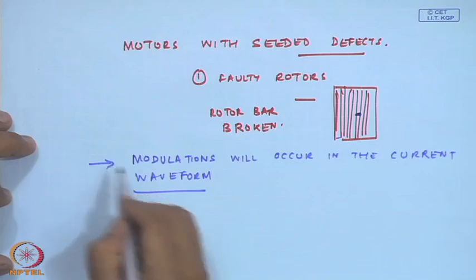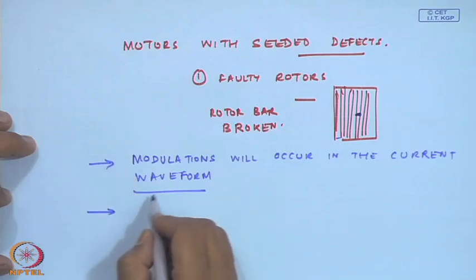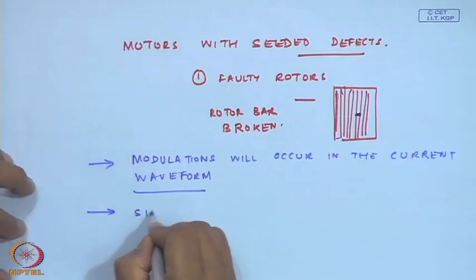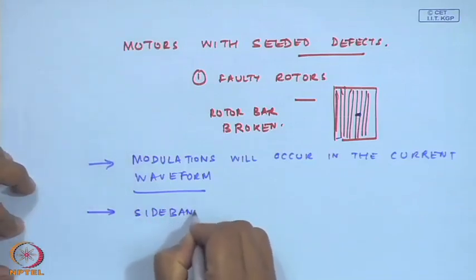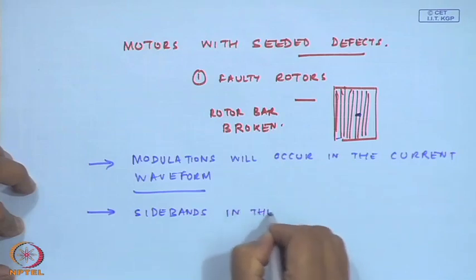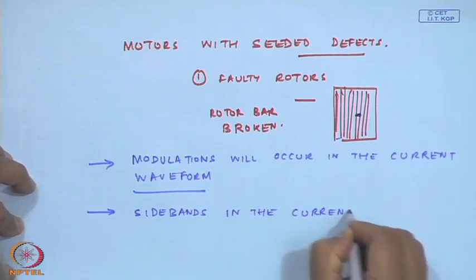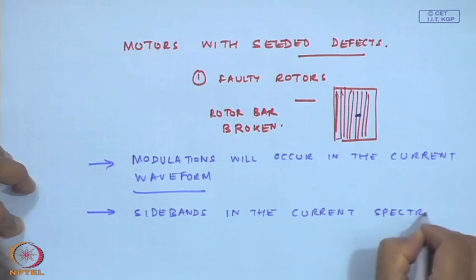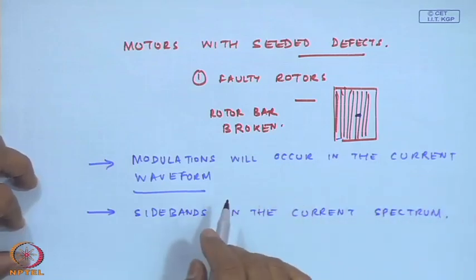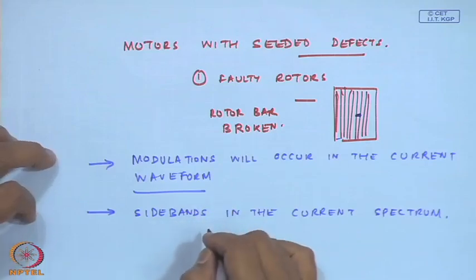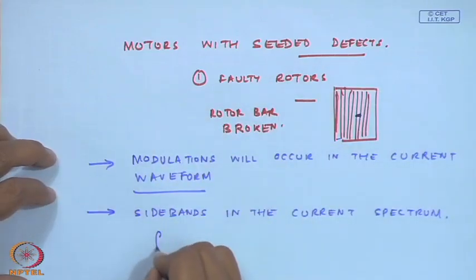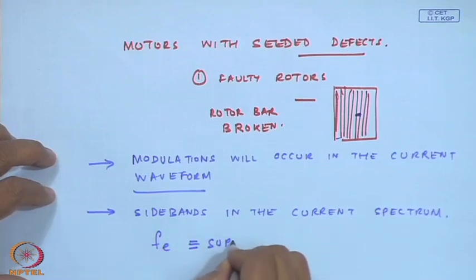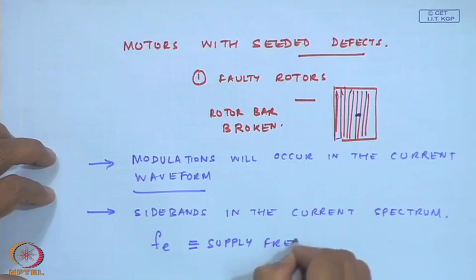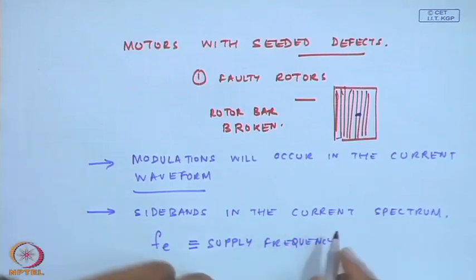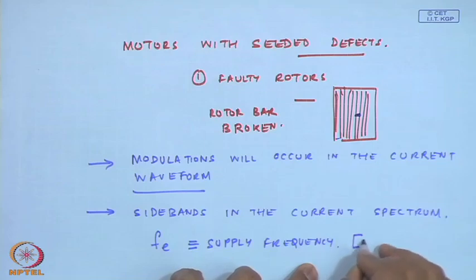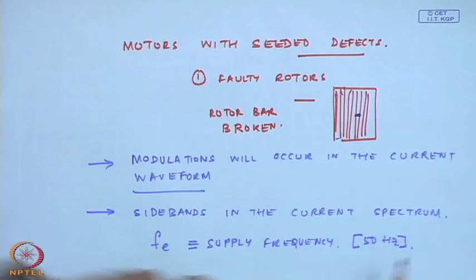And you know from your study of signal processing, modulations in the time domain will give sidebands in the current spectrum. Okay. So, once we see sidebands around the supply frequency, typically supply frequency is FE.